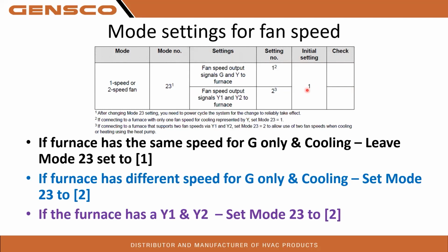Initial settings from the factory are set up for a single stage. So if you're using a two-stage furnace and you're using Y1 and Y2, you're going to need to come into your mode selections and change that to mode 2. That way it actually knows that it's connected to a two-stage furnace and it doesn't just try to run first stage all the time.